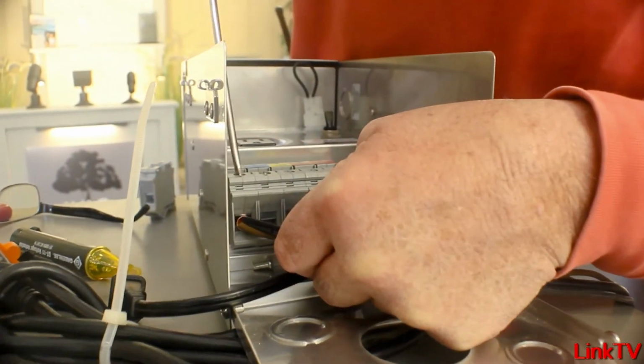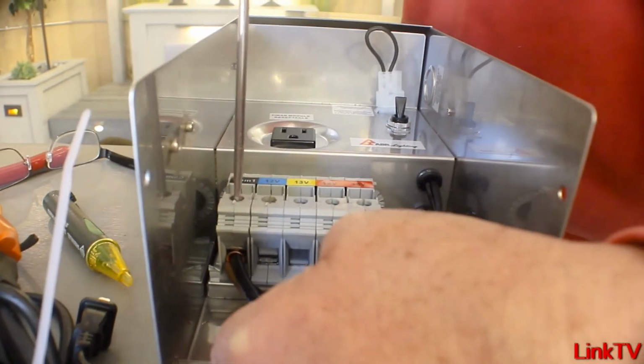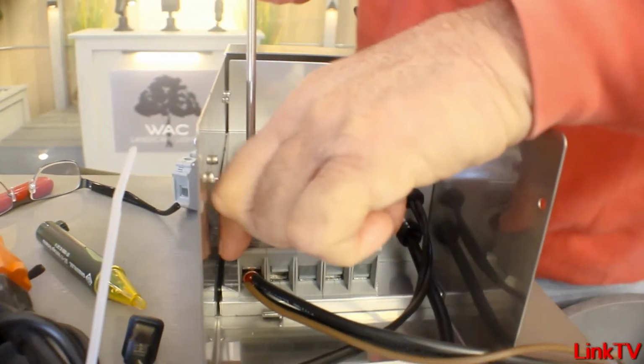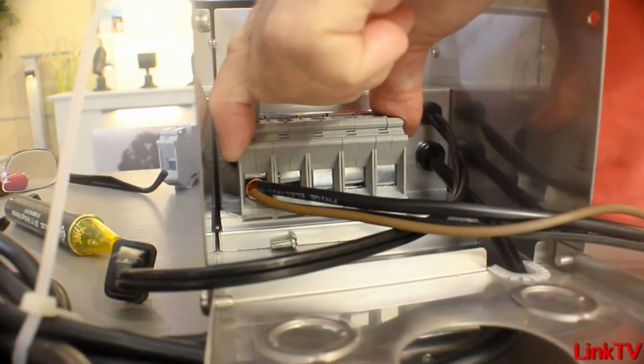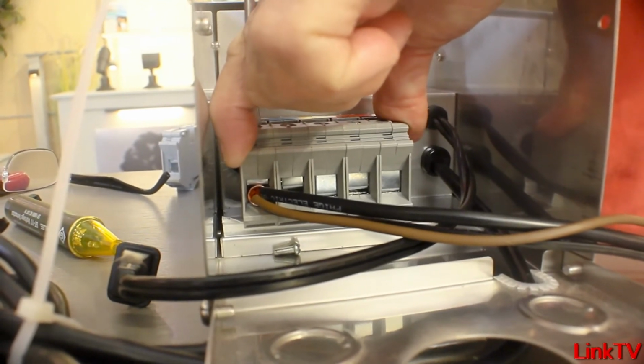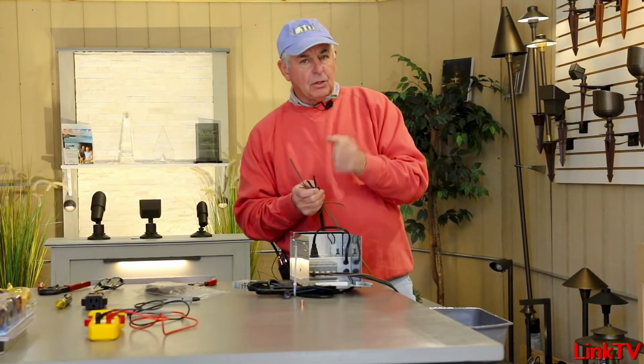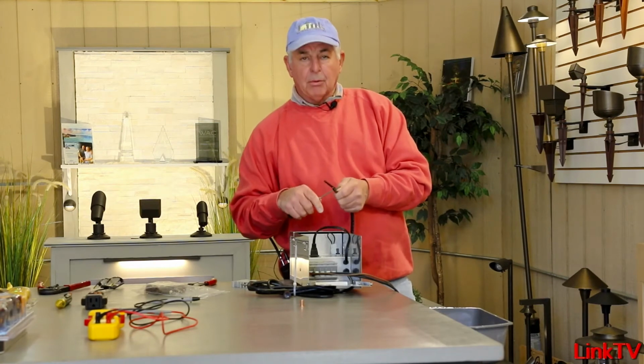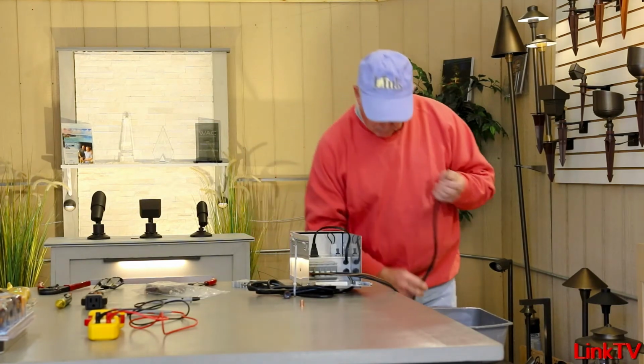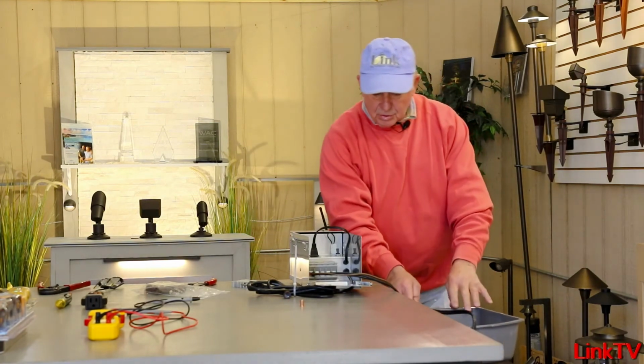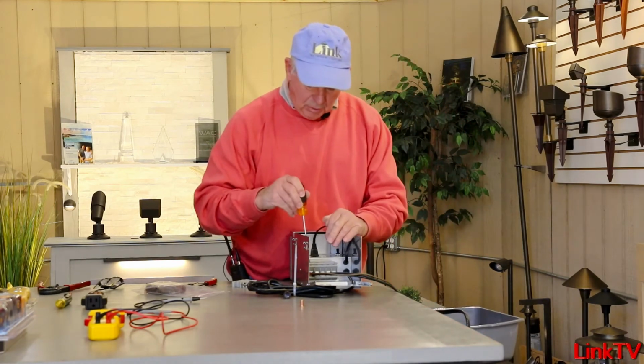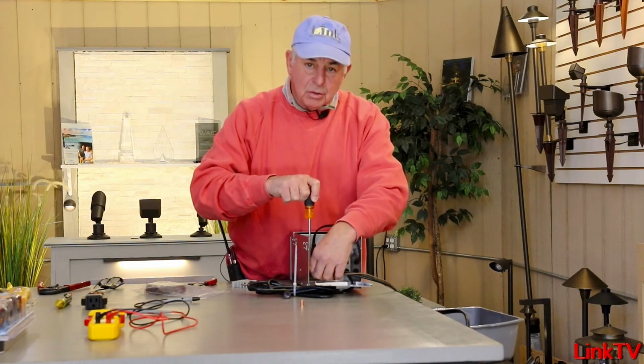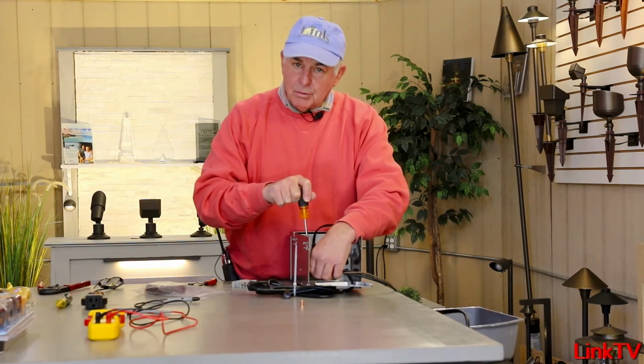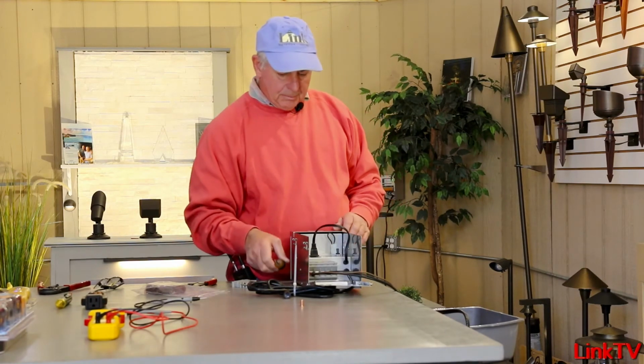You can see how far in you're getting. Here's another thing—a lot of guys push the wires all the way in and clamp on the insulation. They think they got a good bite, but it's really on the rubber, not the copper. That's why this trick is good. You don't have to use it all the time, but you can get it good, snug, and tight, and you'll never have that arcing problem.